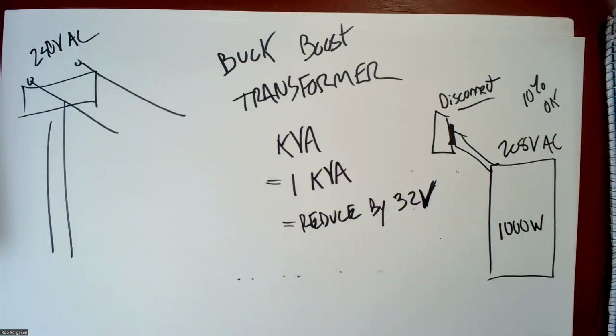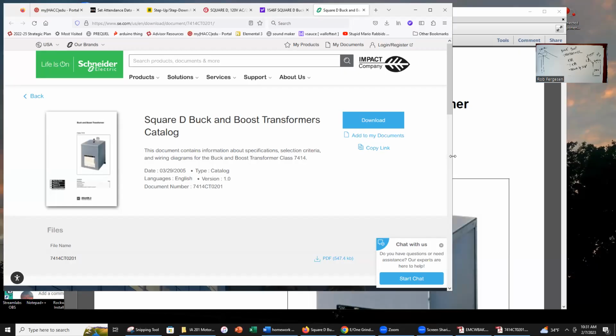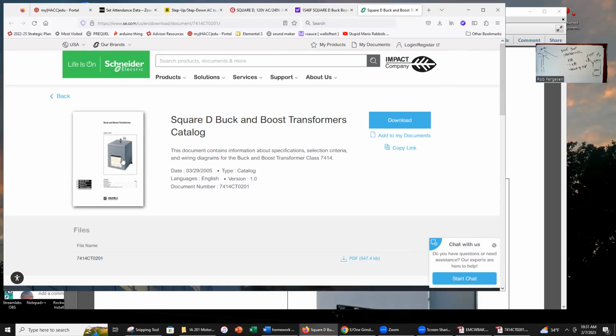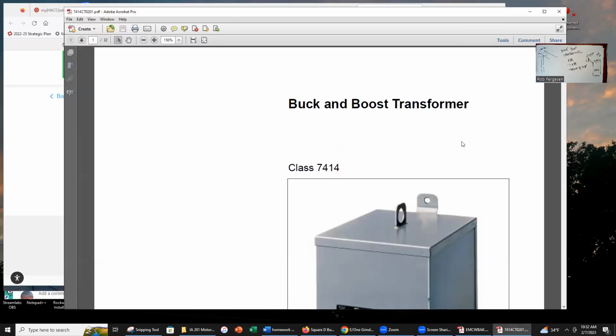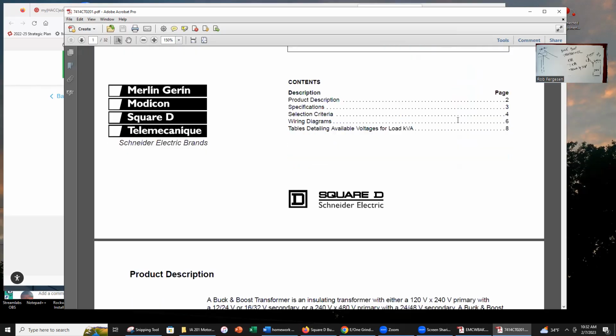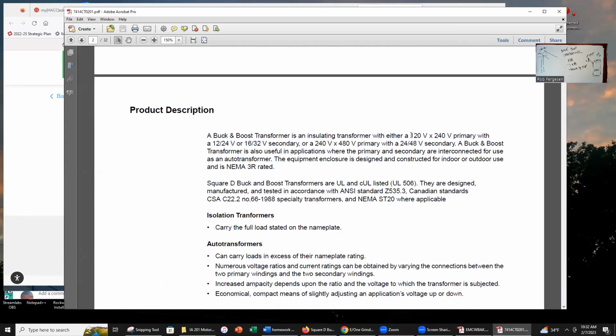All right, so I did a little search and I went to a website called Square D Schneider Electric. So let's go take a look at that website. In Square D Schneider Electric, with a Google search, it suggested this transformer and catalog, which gives me a range of different sizes and configurations. So I'm going to click onto my download for my documentation, and let's click into this document. So this is a class 7414 buck boost transformer. So it can handle 120 or 240 with either a 12, 24 volt or 16, 32 volt secondary.